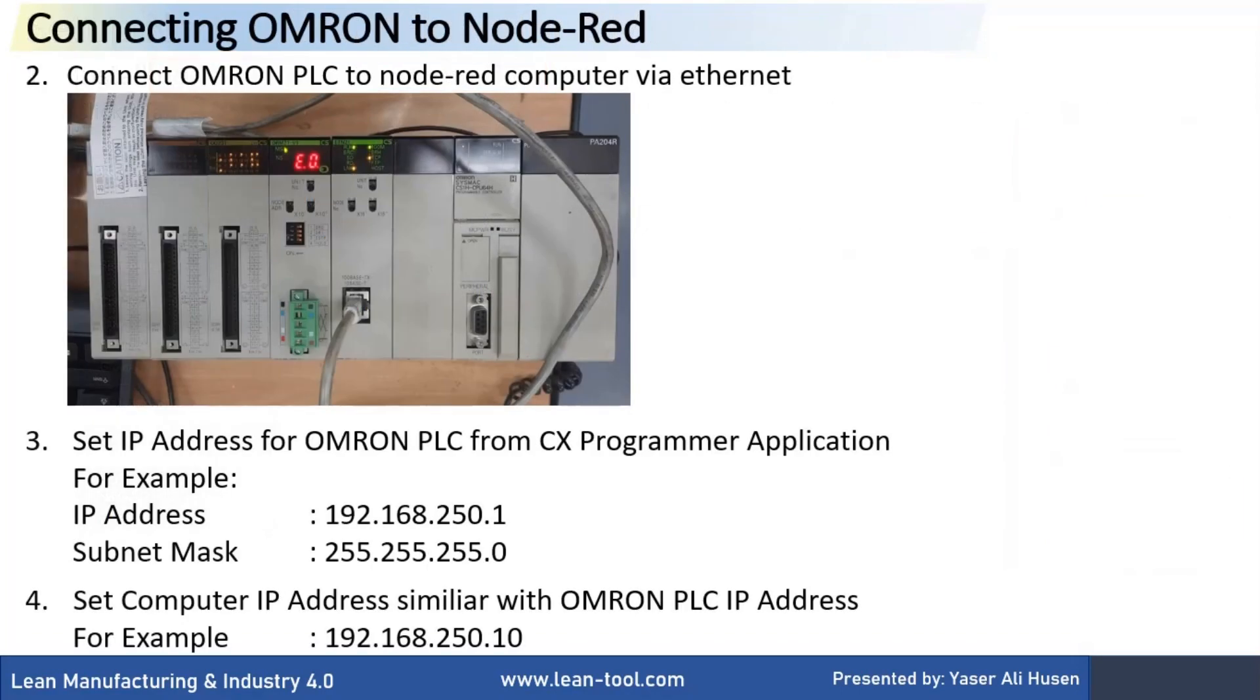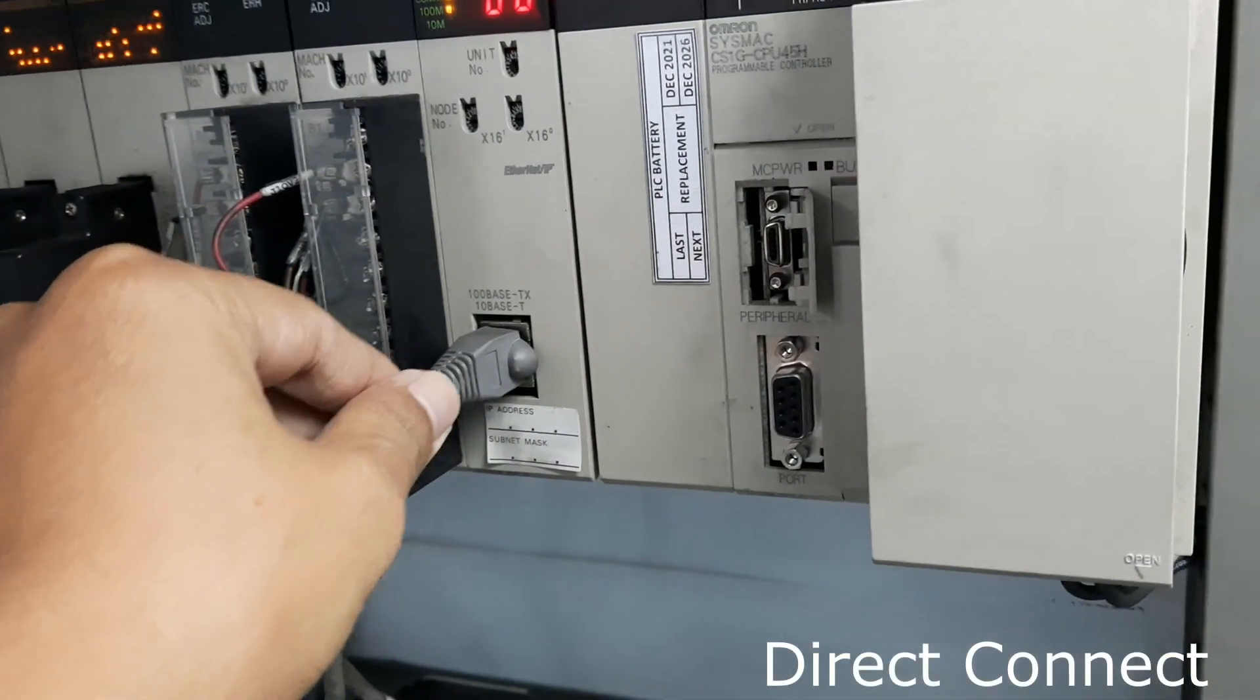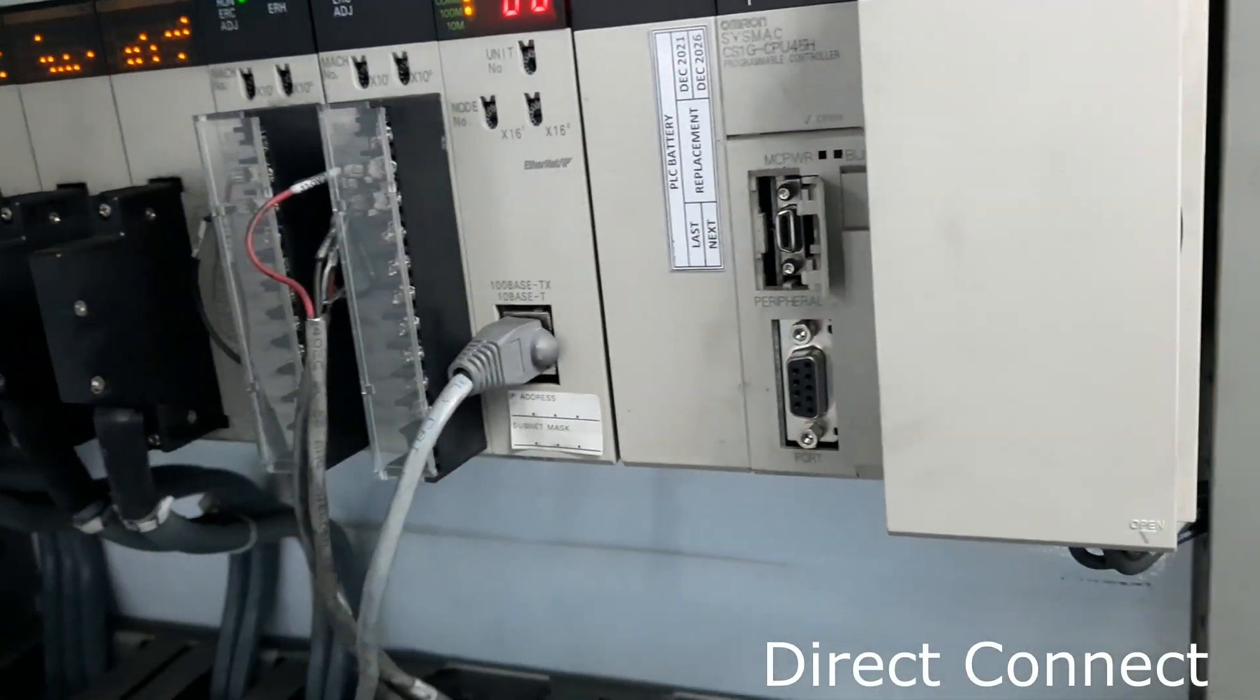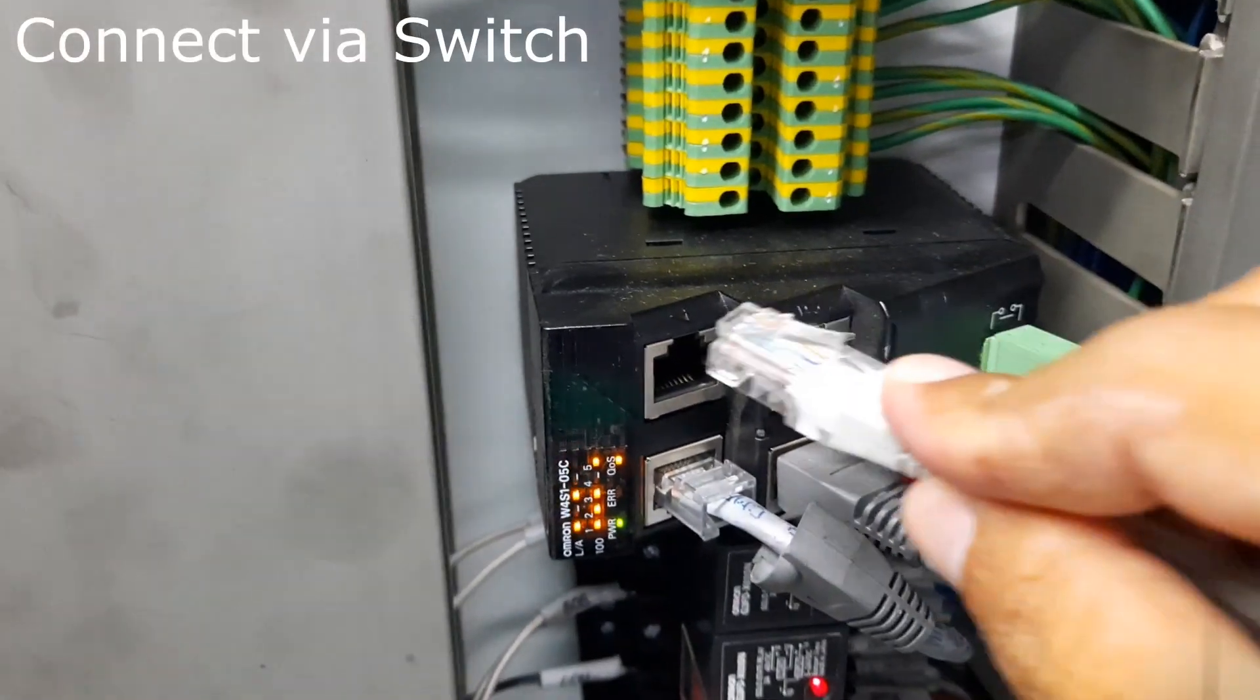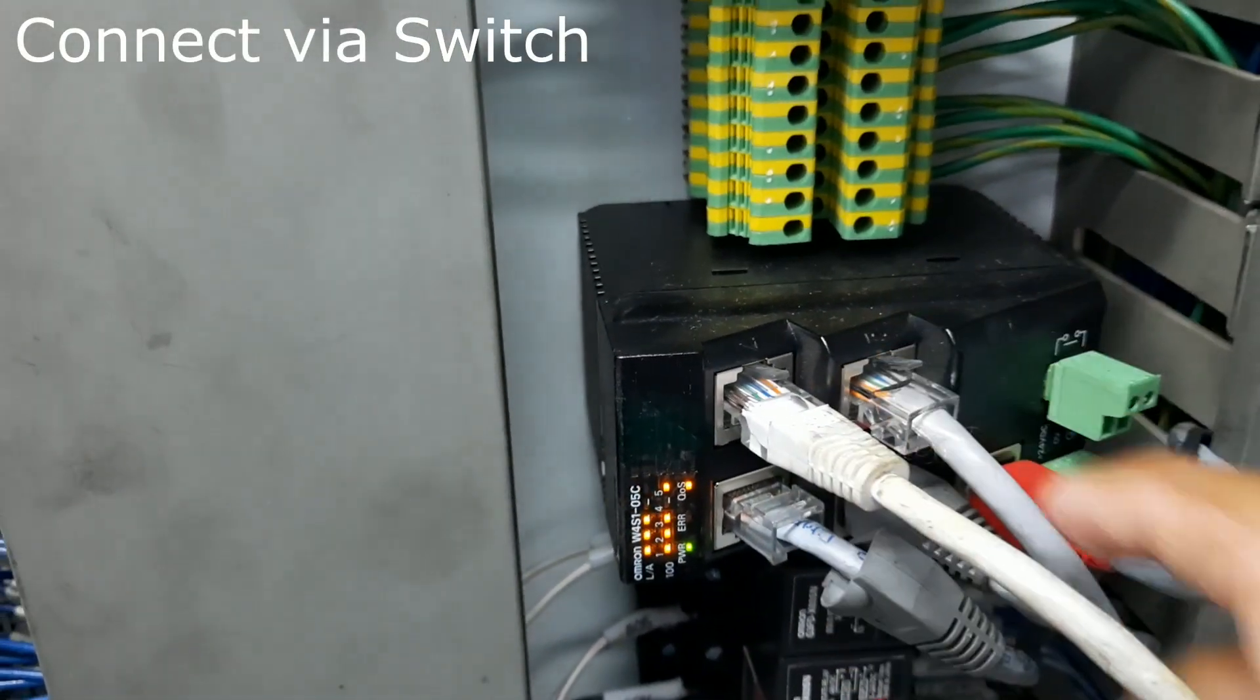For connection, we use Ethernet connection. Set IP address for Omron PLC using CX programmer application, and then set Node-RED computer IP address similar with PLC IP address. We can connect directly to PLC, or if we want to connect to multiple PLCs, we can use a switch hub.